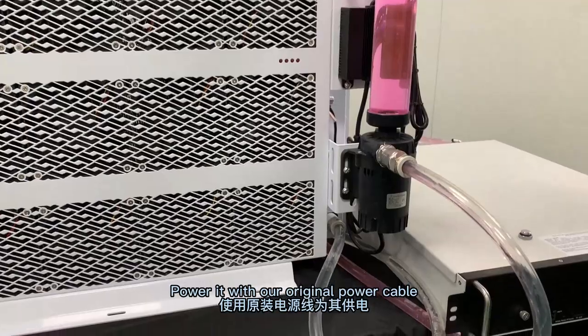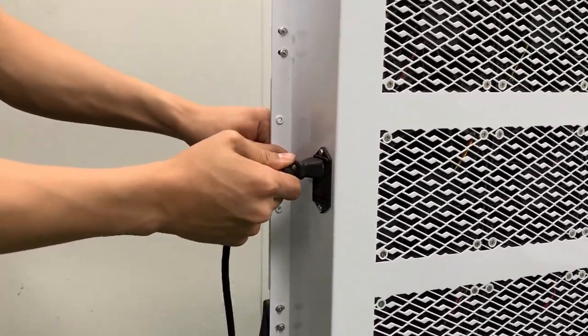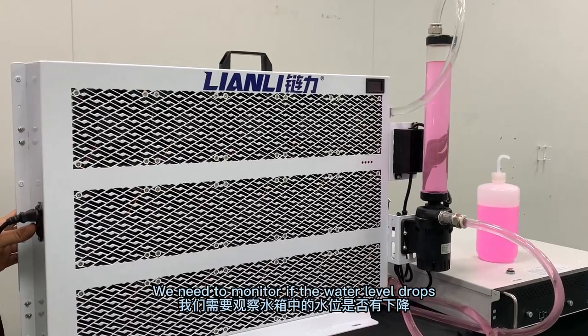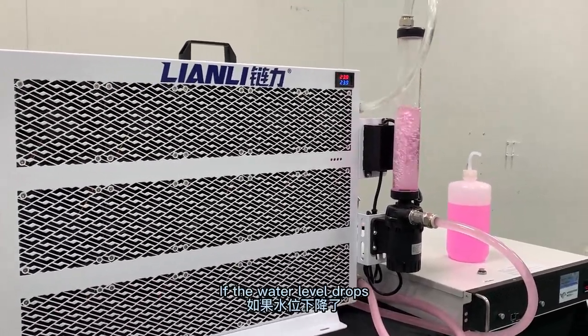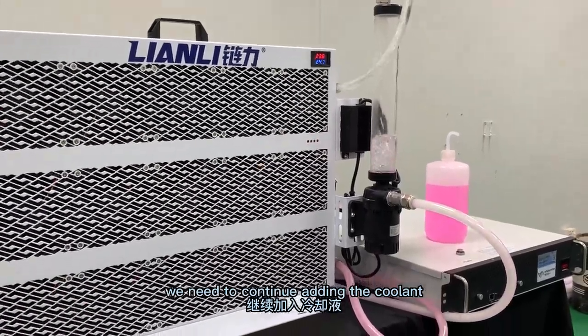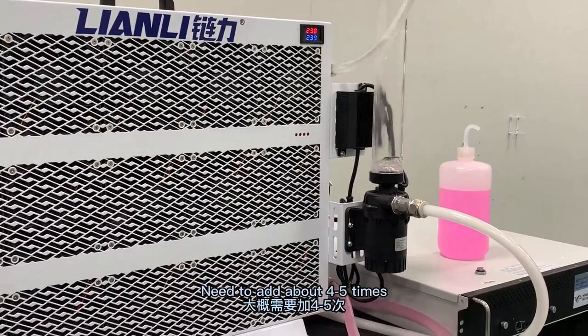Now using the bottle to fill the pump. Power it with our original power cable and let the air out of the radiator. We need to monitor if the water level drops. If the water level drops, please continue adding until the level does not drop. You need to add about 4 to 5 times.